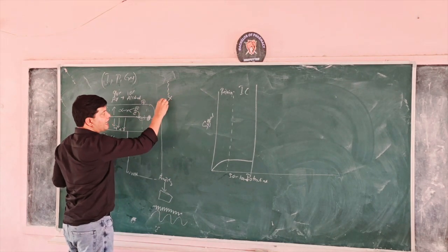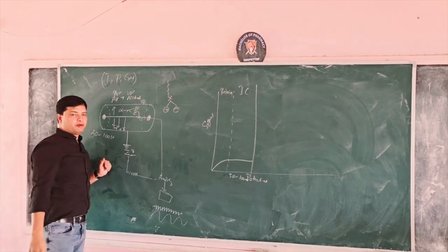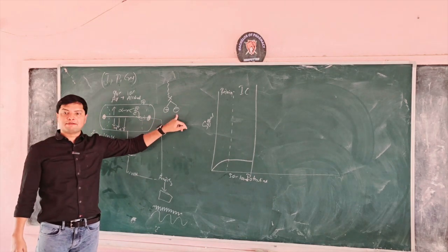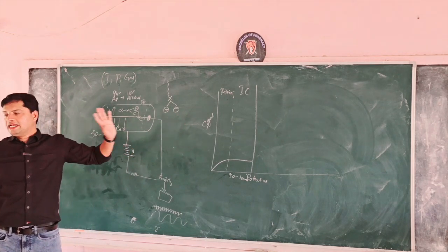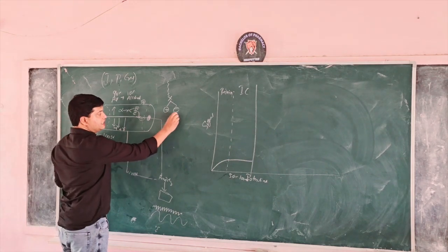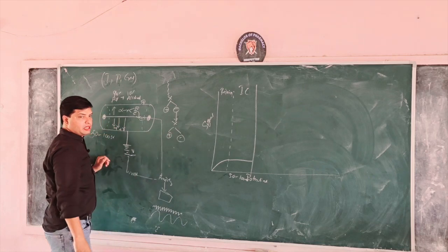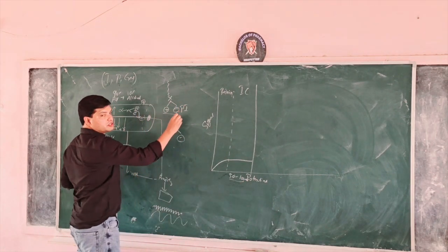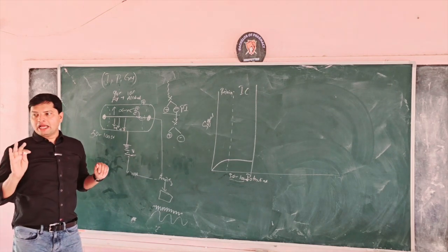Now, when the radiation hits the gas molecule, it will produce ions. We call these primary ions. It will only produce primary ions. No secondary ions are produced. What do you mean by secondary? The ion would go and hit another gas molecule and again produce ions. In the case of the ionization chamber, if you apply only 50 to 100 volts, only primary ions are produced.